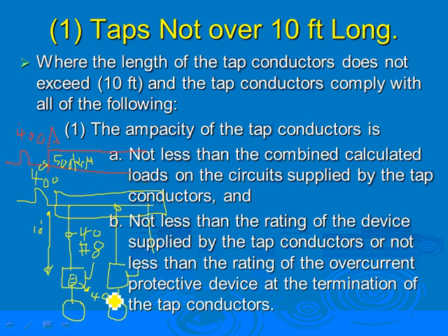Any comments, any questions? Yeah, one of the problems that I found is people will set a disconnect switch 10 feet away. The problem is the code states that the length of the conductor shall not exceed 10 feet. So from the actual, physical tap to the top of that disconnect switch is where the 10 feet is measured. From the conductors, absolutely. And so if you measure from here to the disconnect, you probably have to add another 6 inches here, another couple of inches here. So when everything is said and done, you're really looking at probably 9 feet between enclosure to enclosure.